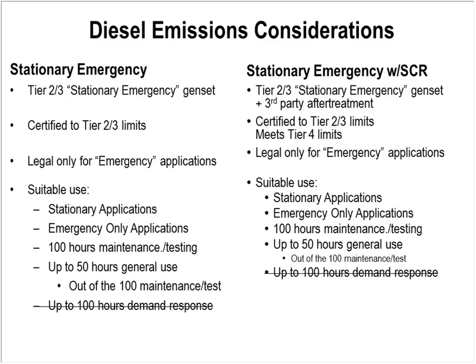Just to compare the stationary emergency with the non-emergency or Tier 4 certified, as we've discussed, restricted operation on the left for stationary emergency. Stationary non-emergency or Tier 4 can be used for both stationary and non-road mobile applications. It's fully certified to the full Tier 4 limits. It's legal for use in emergency as well, but essentially it can be run for unlimited use in continuous or prime power applications. So that's 24/7, 365 availability of power for unlimited operating hours.